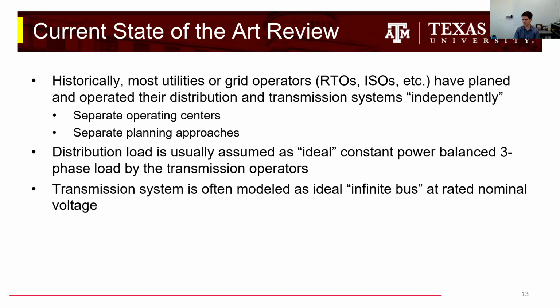And for the distribution system operators, they usually view the transmission system as either an infinite bus or some model incorporating the short circuit ratio, some variation of a perfect voltage source behind some reactance, whether subtransient reactance for fault studies or synchronous reactance for the point of interconnection, the strength of the grid. But it's just assumed the transmission system can supply as much power as the distribution system needs.